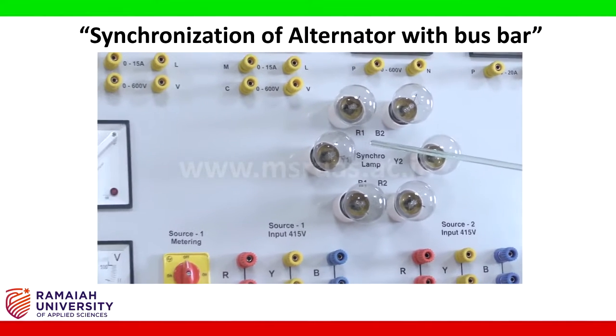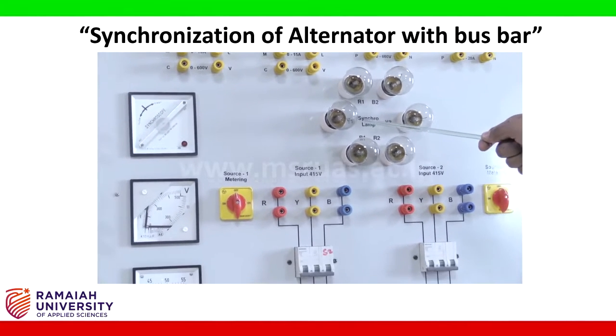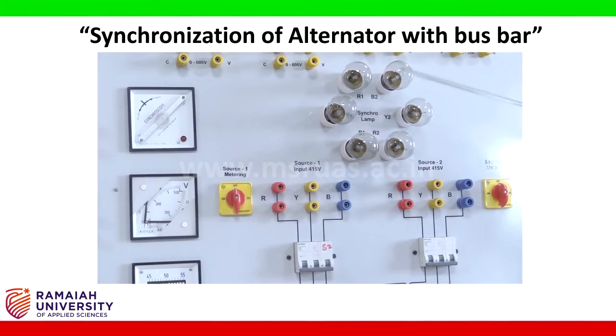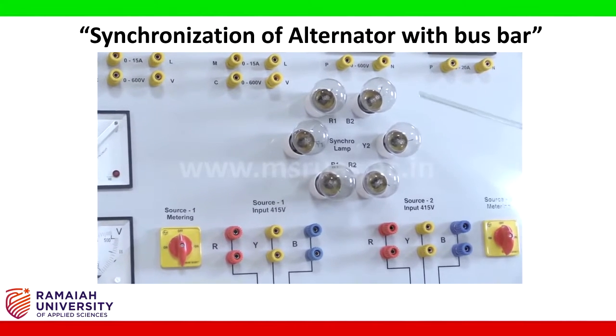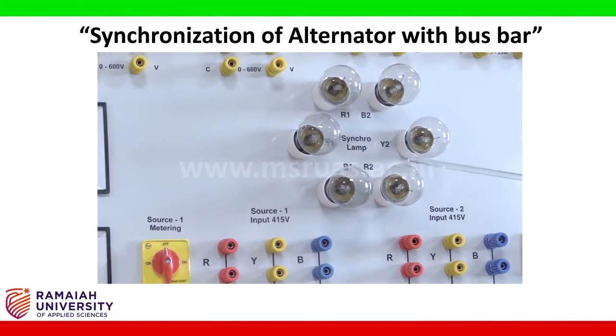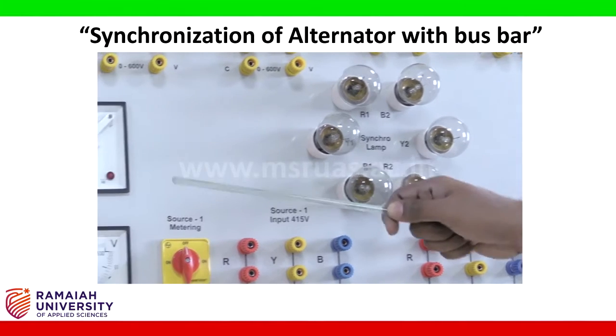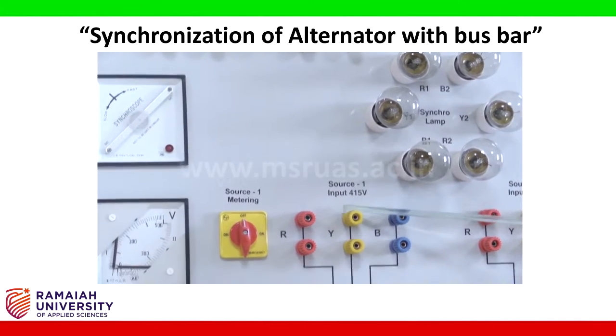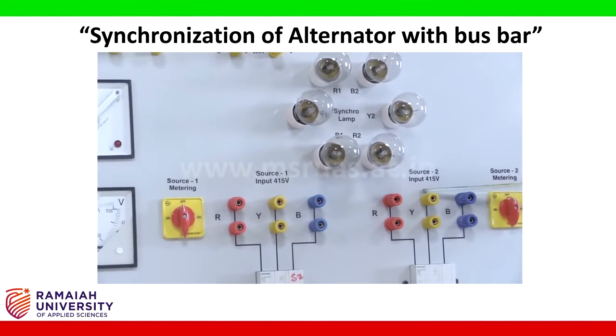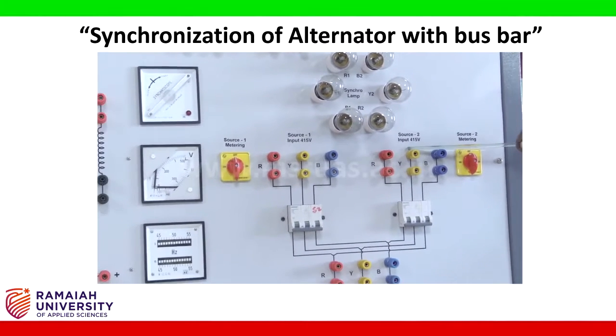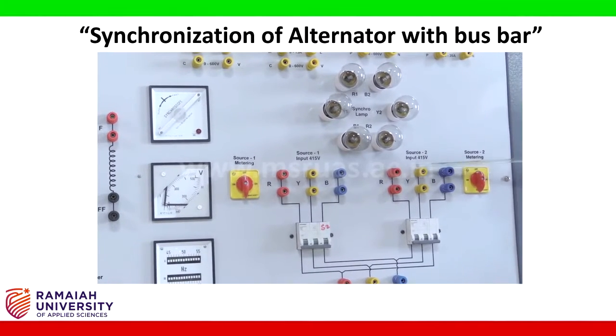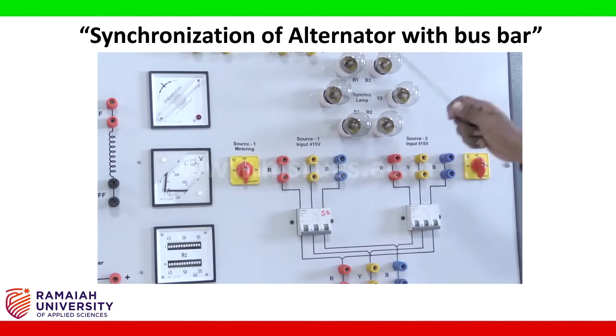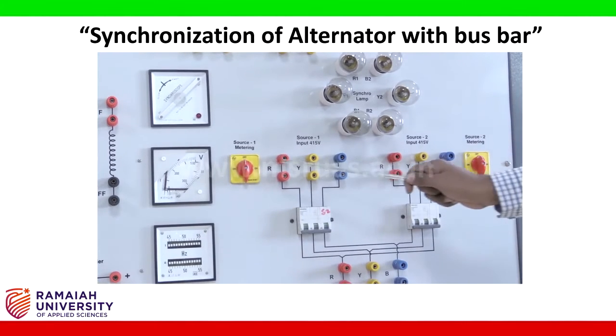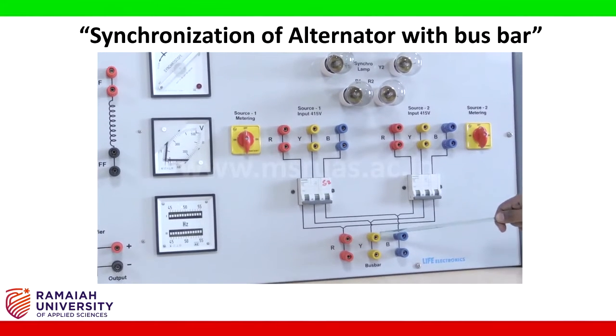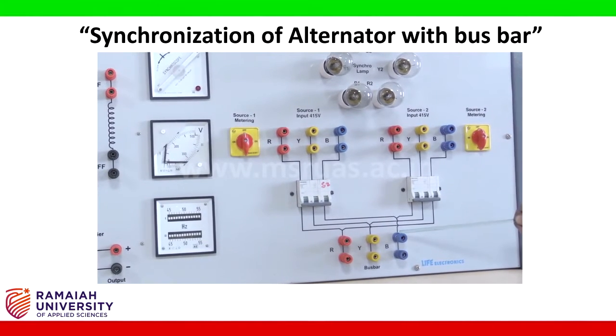Here, in order to observe the synchronization very clearly, we are having lamp setup. 6 lamps are arranged, 2 for each phase. You can observe 6 lamps, 1, 2, 3, 4, 5, 6. The incoming alternator terminals are brought here and the existing system terminals are brought here. When all the parameters are in agreement, we will close the switch and we will synchronize our alternator with the infinite bus. These are the two on-off switches provided for source metering. Here these are the output terminals. From this we can load our alternator.